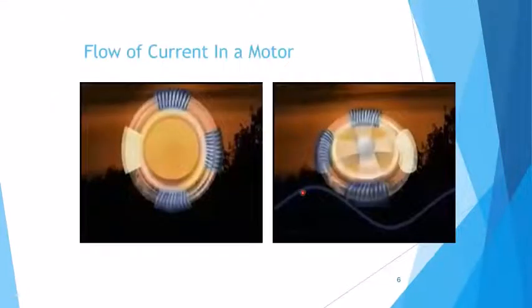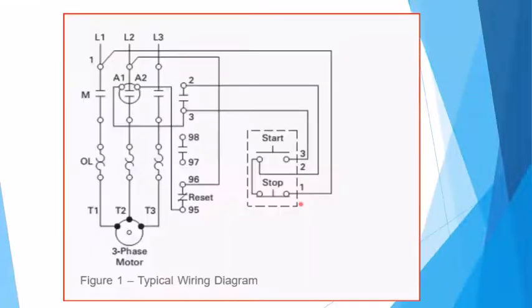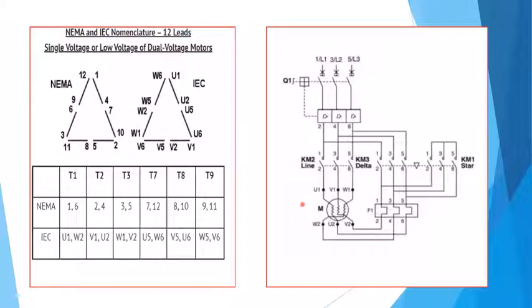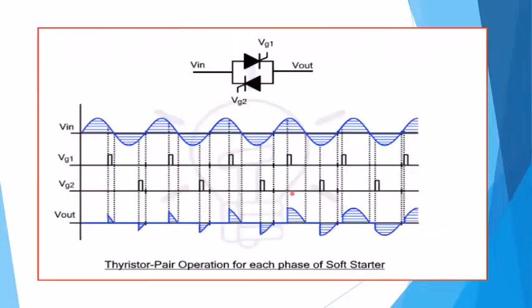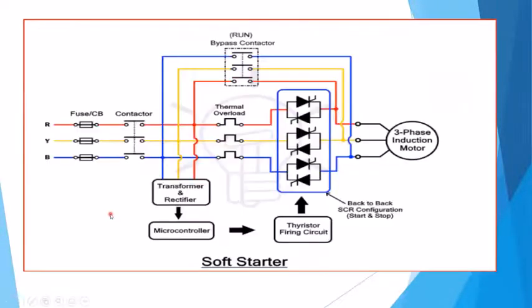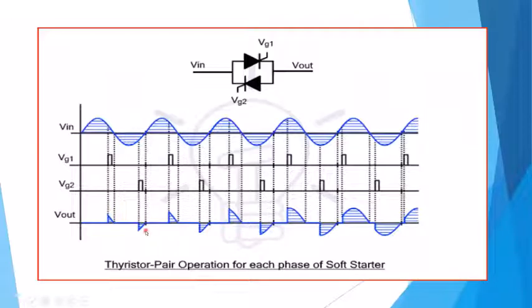So again, back to our original sine wave power that we were creating back at the generator. So here we go. What was happening is, here was our sine wave that we were getting, the AC voltage from the power source, and we could tell this device in both the positive direction, meaning here going positive, or negative, we could tell it when we wanted how much of the waveform to actually get to the motor. It did soft starting. A tremendously helpful device.